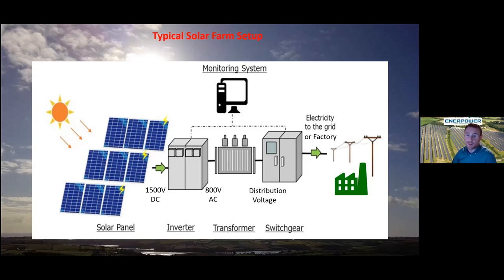There's over 4 kilometers of AC cable on site, so we have to bring them all back, then step them up to a distribution voltage. In this case, that distribution voltage is 10,000 volts, so the transformer takes it from 800 volts AC up to 10,000 volts, which we'd deem medium voltage.